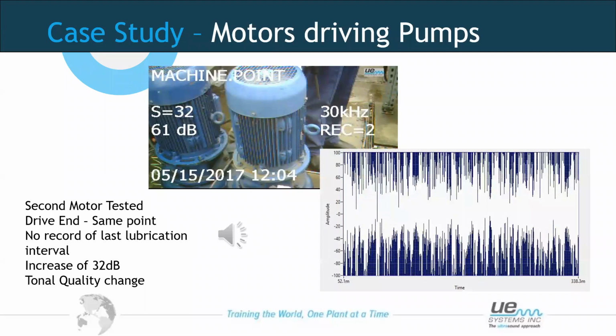As we can see from the screenshot here, from the time series, we can now see a very large increase in amplitude. And also, it no longer looks smooth and uniform in nature. So again, this is indicating that there is something not right with this bearing on this motor, and they should be very similar in amplitude and tonal quality. So again, we can see here that this bearing would show concern to us.